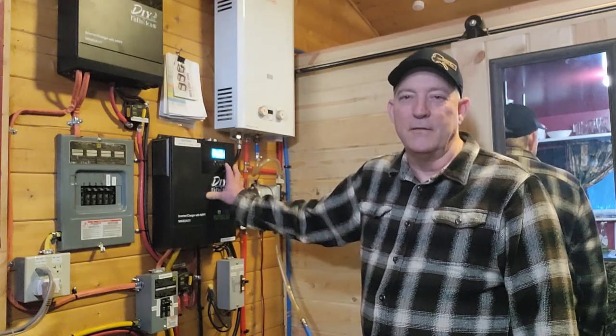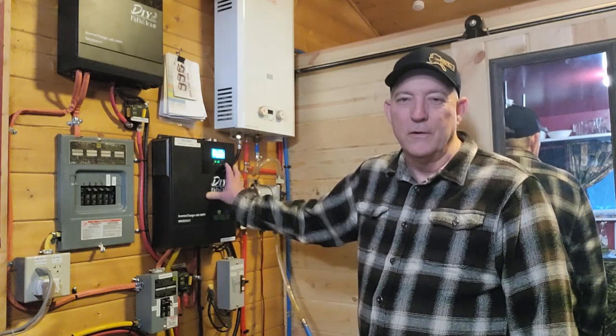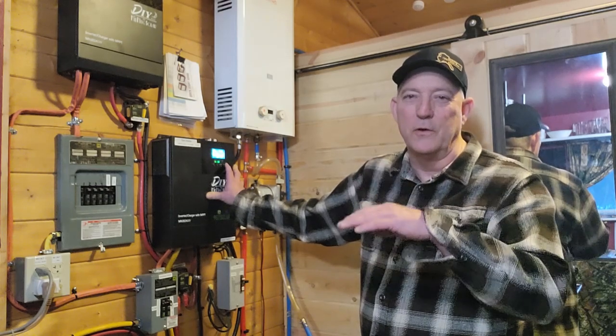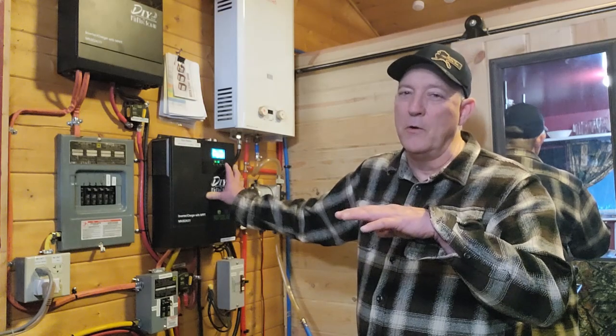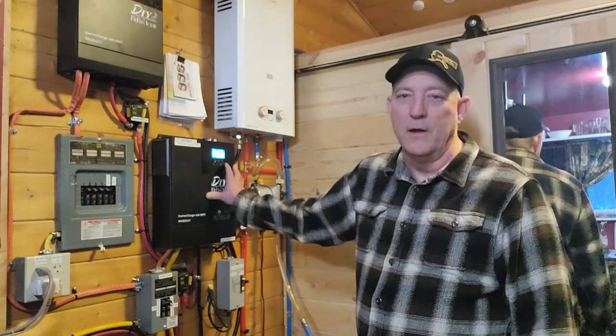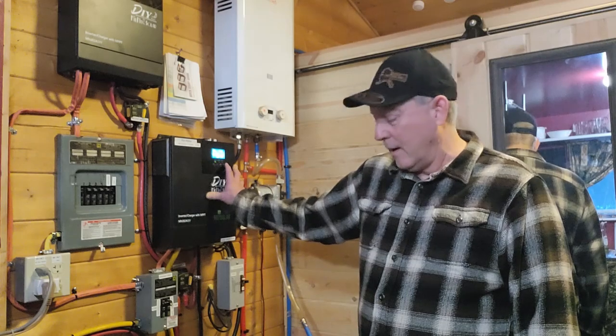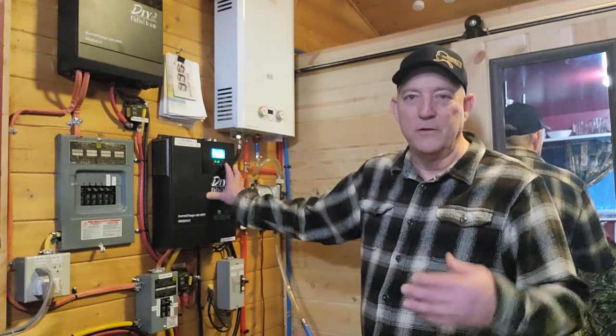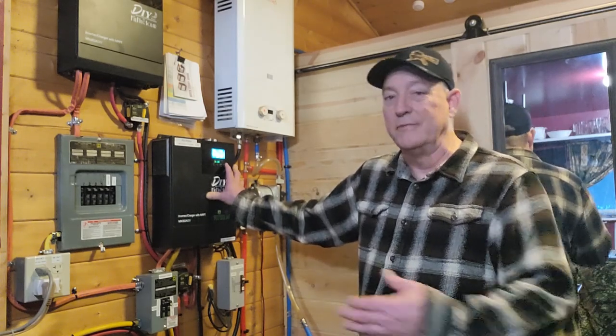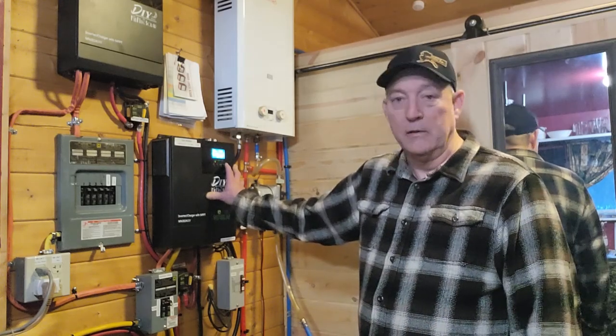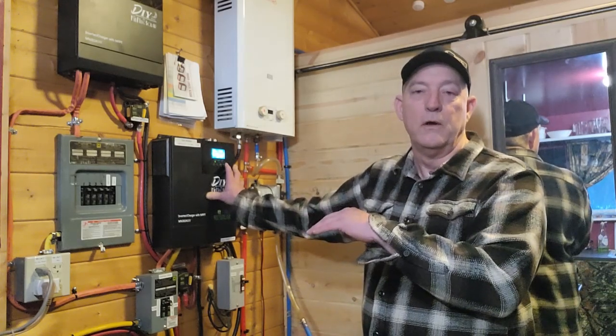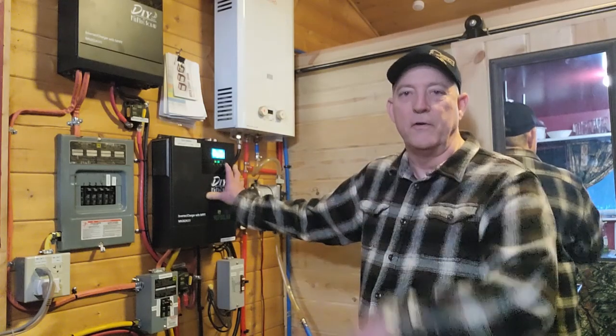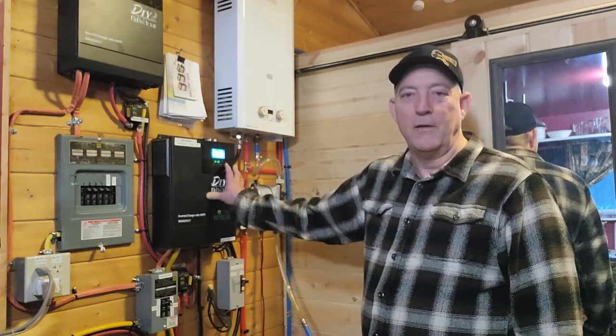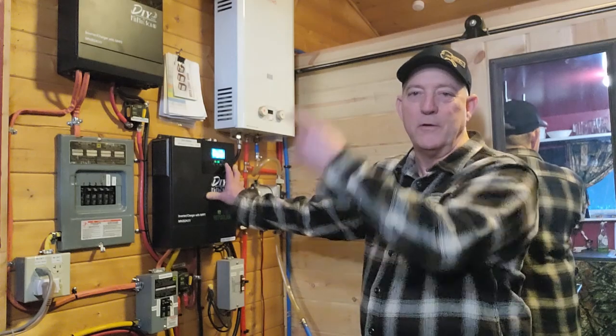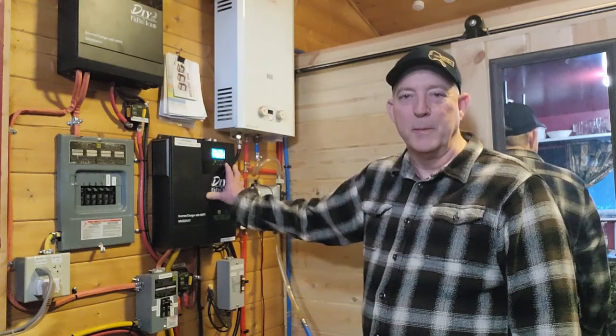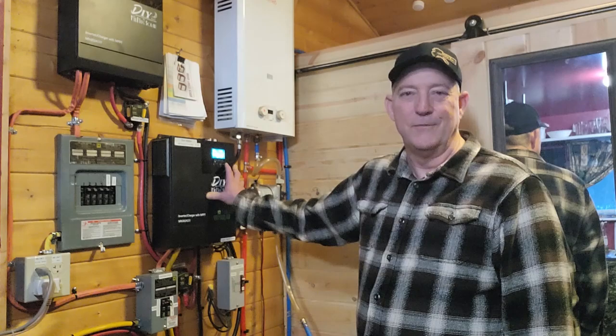I've got it set right at 24 volts. Once it powers down to 24 volts, I can go down a little bit more, because with lithium you can run almost 90% of its battery before it just cuts out completely, or at least that's what I run mine to. You lose some, but I sit at 24, so it gives me a good buffer. I don't like to get woke up in the middle of the night and come turn these batteries off in the inverter and charge it up in the morning. No, we ain't doing that.